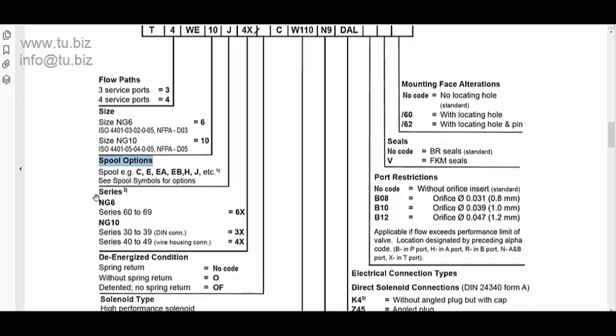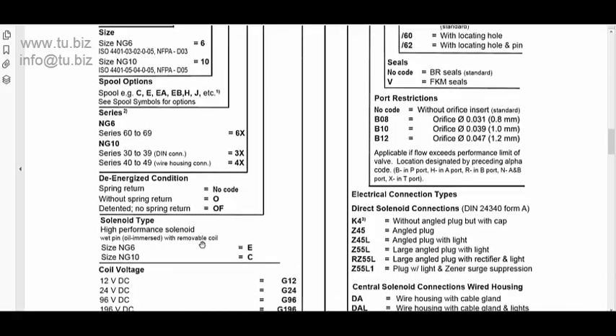You have then the series. This is a standard for NG6. I call it D03. It's the same thing. It's a 6X and the NG10 or D05, it has an X3 or X4 depending on what type of solenoid connection you want on the coil. If you want a DIN solenoid, which is the standard, you have a 3X. And if you want just an open wire, then you have a 4X.